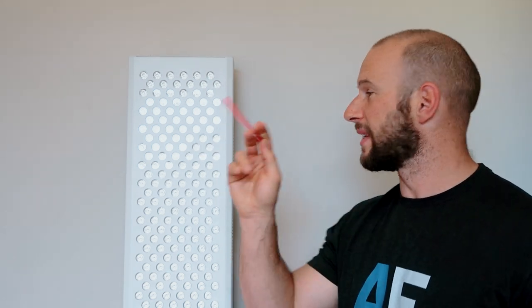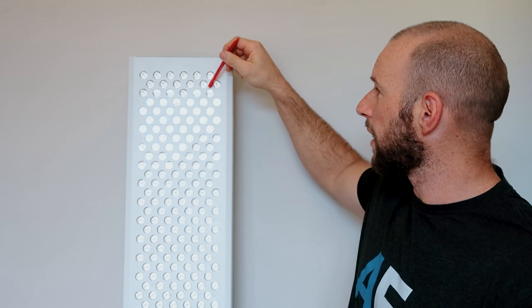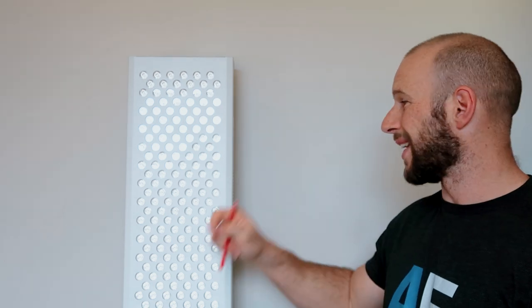Next, I do an average combined irradiance figure. I measure nine points on a panel and take the average reading. I take six readings around the edge — coming in about an inch diagonally from each corner, two readings per side, one on each side at mid-height — and then three readings through the middle. When I'm doing it, I hover around and try to get a stable average; if I see something really high like 60 and all the rest are around 38, I'll ignore that 60 and just get a stable reading.